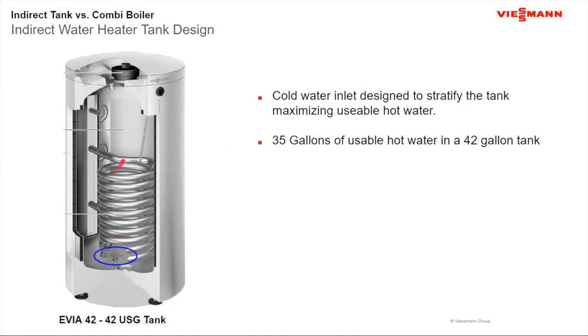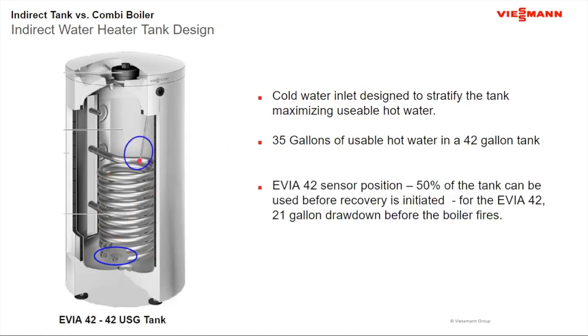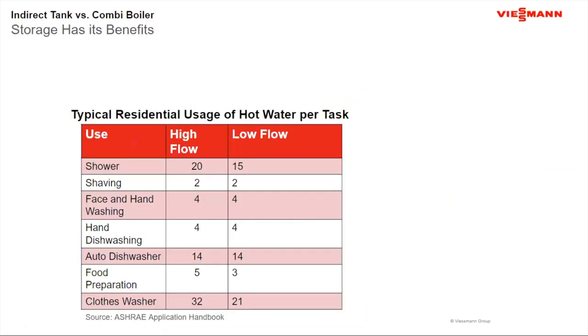Additionally, when I'm using that hot water, it's not where I start to draw the hot water and the boiler immediately fires. Over here, I have my well with my sensor. The sensor comes down about halfway in the tank. So in that halfway position, I can use about 50% of the tank's volume before the boiler comes on. So it takes a lot of draw, a lot of hot water usage before the boiler is actually going to fire. So that means I got about 21 gallons of usable hot water. When the boiler comes on, I still have about 15 gallons of usable hot water still to make my way through. So it holds it off, it delivers the hot water, and then when it starts to recover, there's still water available.